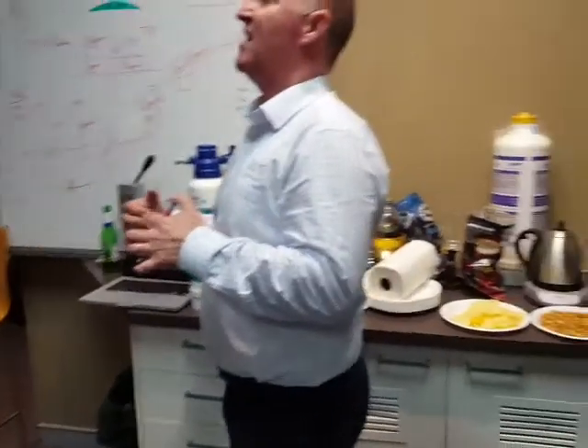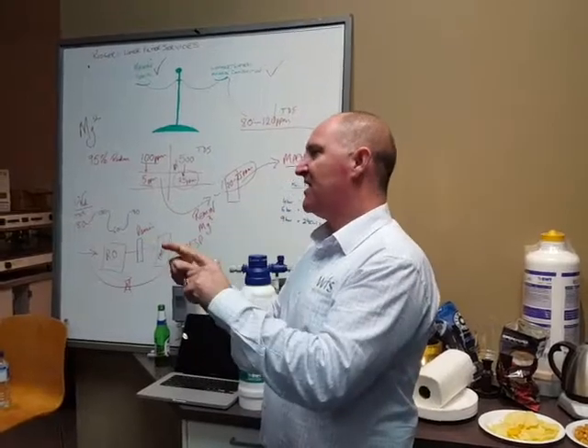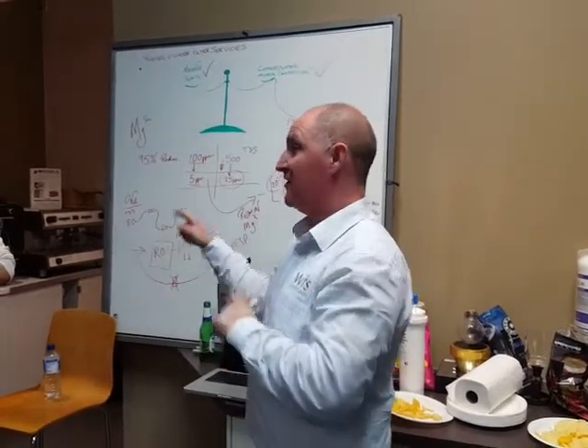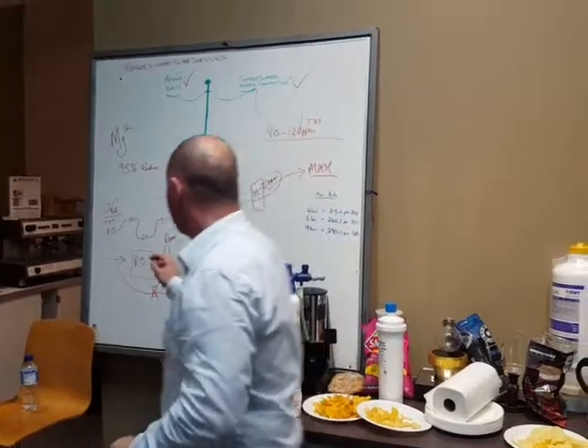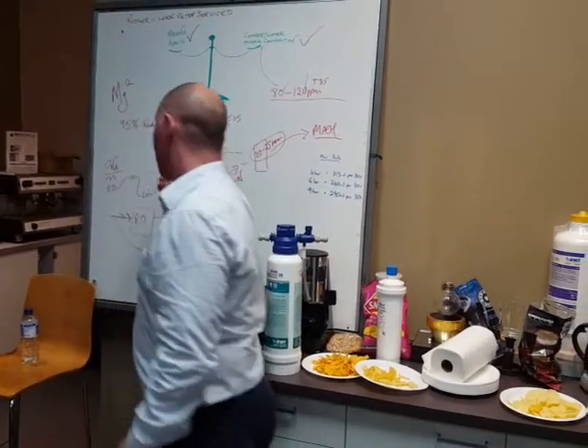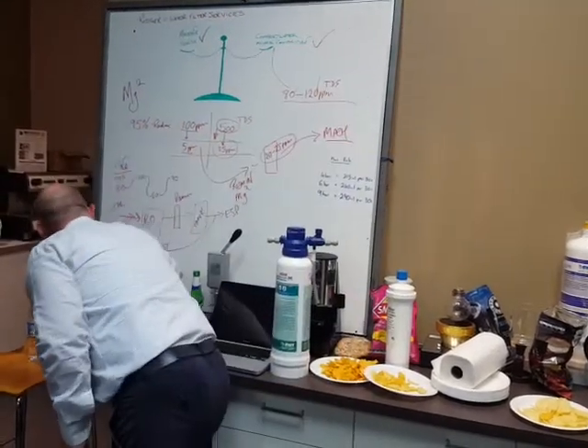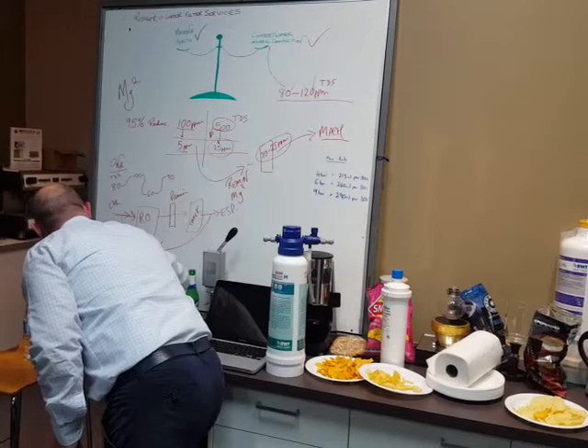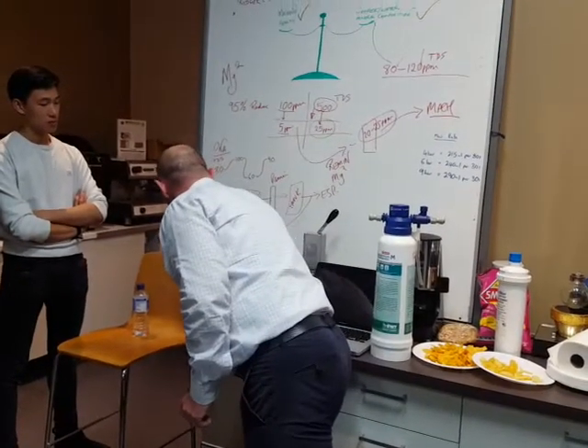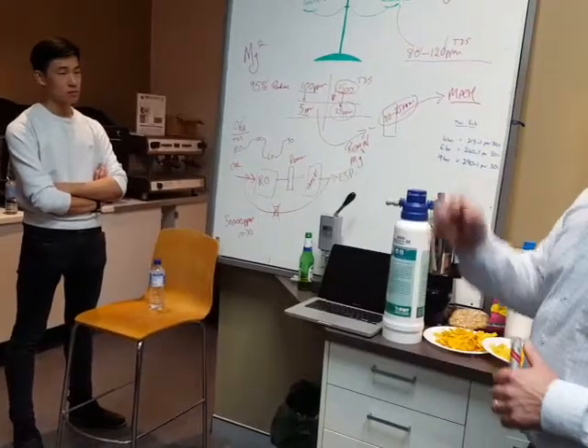And the testing that I've done so far in the 6 years that I've been involved in this industry, I cannot get a needle valve to deliver the same blending percentage through low flow or through high flow. It changes. Also, the reason why you're putting the water through an RO is because of the nasties in the water, and you don't know what they are. If there are chlorides in the water, does anyone know what chlorides are? We don't know. So 50,000 parts per million of chlorides is salt water. In Sydney, there's anywhere between 20 to 30 parts per million in the water. That's still enough to put pit holes through a boiler.